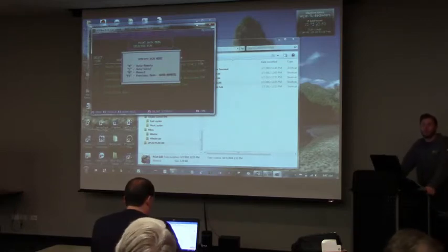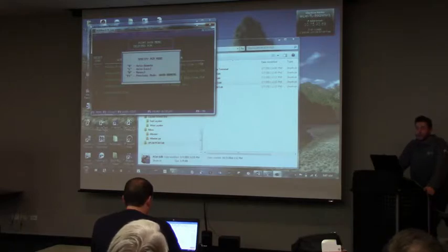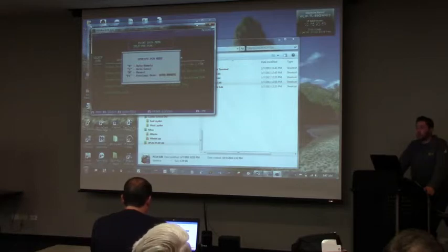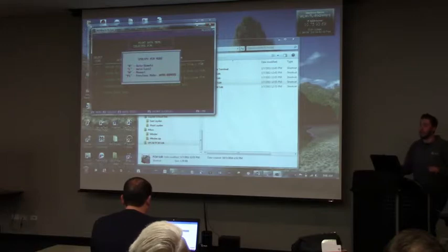So you have to make sure if you're running auto local that you've got the default values for all your set points right. And then I have been to quite a few job sites on Tracer Summit where the customer puts in the manual control and he's wondering why things aren't working right, because once you put in the manual mode, whatever you set those values to, it's staying that way. It's not moving at all.